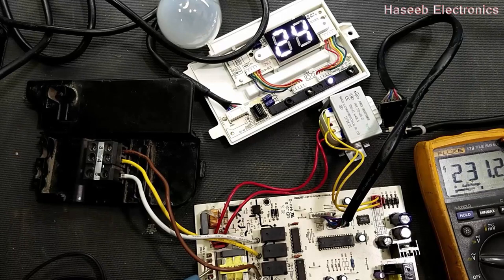And now we can check the voltage at this fan, and we have 231 volts for the fan. So that means the fan should run. So our board is now recovered. We don't have to replace this.